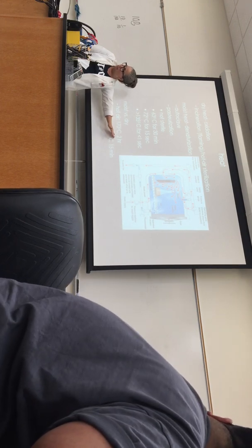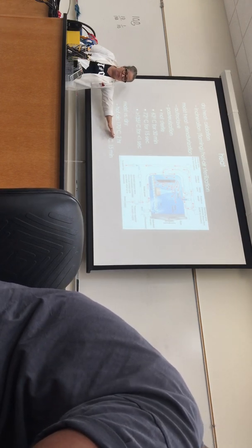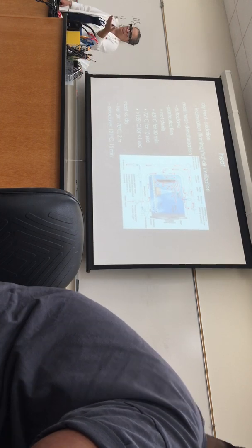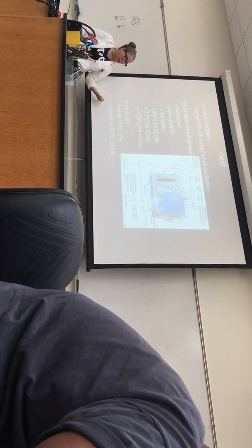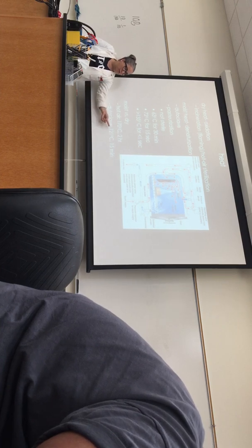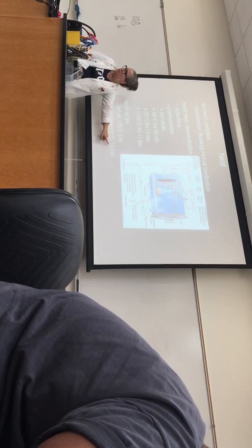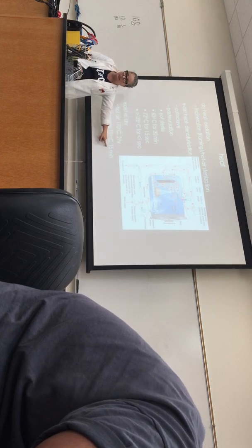I don't know about you, but I really don't want to sit here for 2 hours after we're done waiting to do something. So what if I just add moisture? If I add moisture in an autoclave, 121 degrees, so that's nice, doesn't have to get as hot, and look at this, 15 minutes. That's how much moisture changes that.